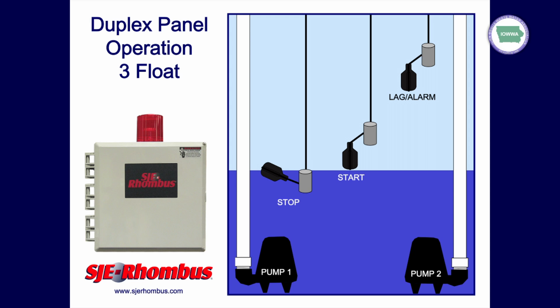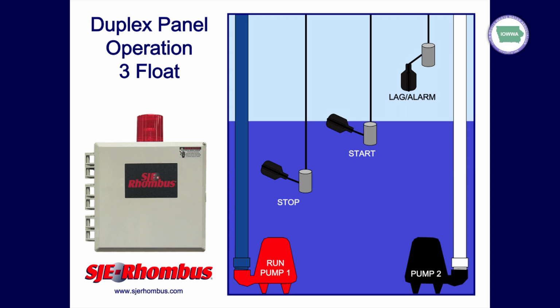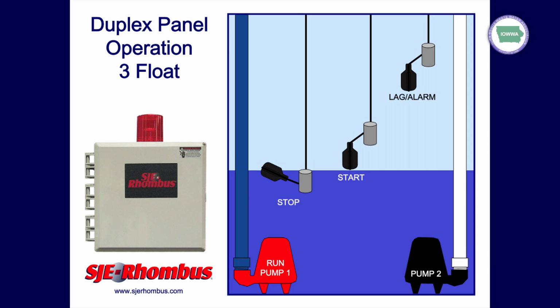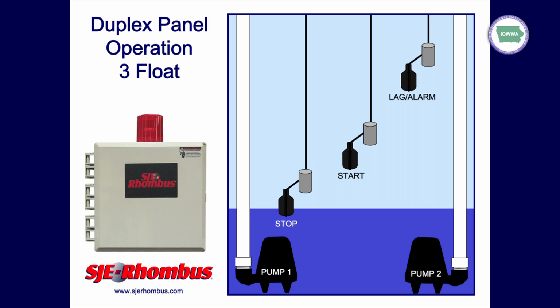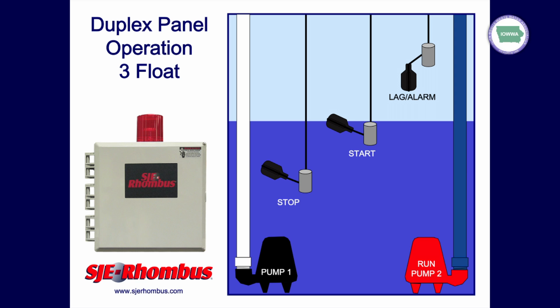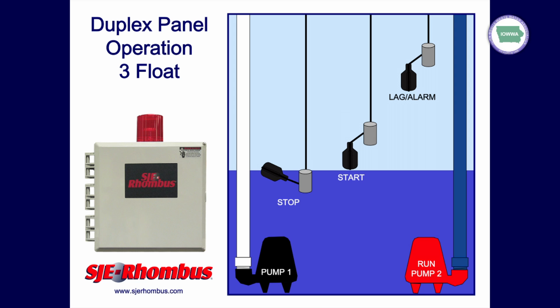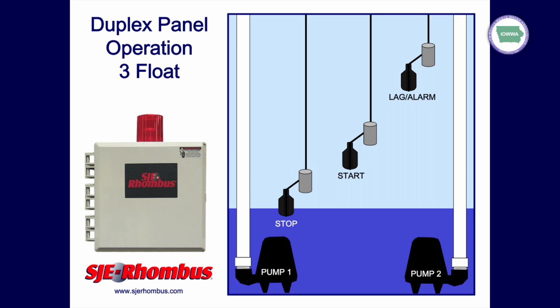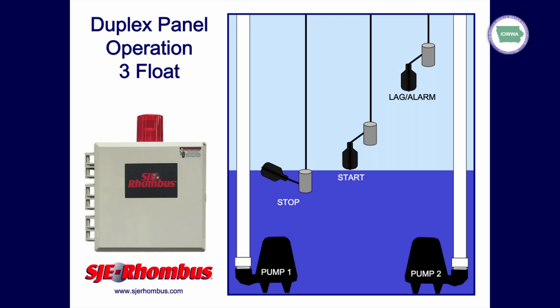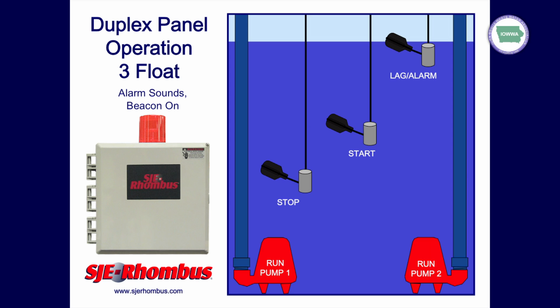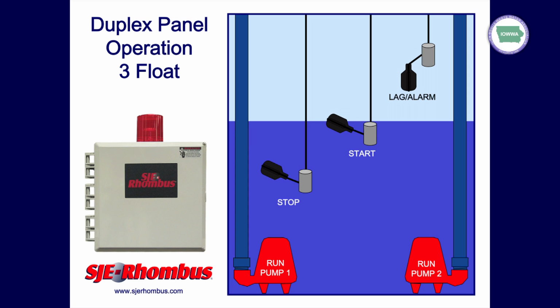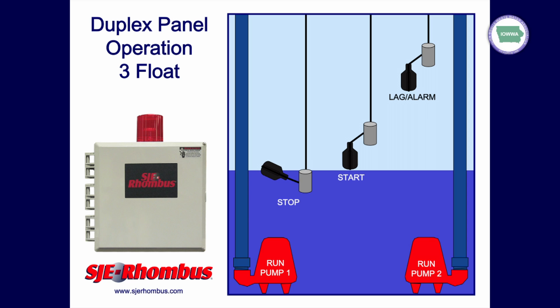With a normal duplex system, when the start float is reached, 1 pump's going to turn on. It's going to operate until the stop float drops back out, and then it shuts off the pump. Next time around, pump number 2 is going to run, so you get even wear and tear out of both pumps. We're going to alternate back and forth between the 2. If we reach the lag point, you can see right there we've got 1 pump running. Once you reach the lag point, it's going to turn the second pump on, and they're going to run simultaneously until we hit the stop float again.